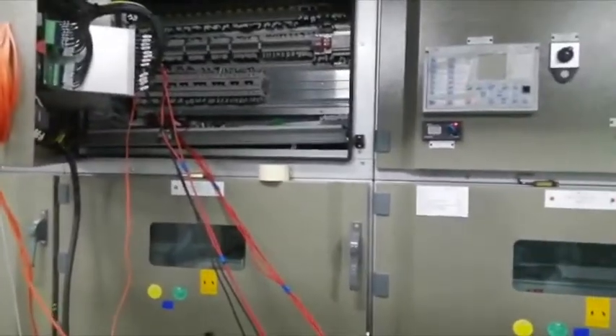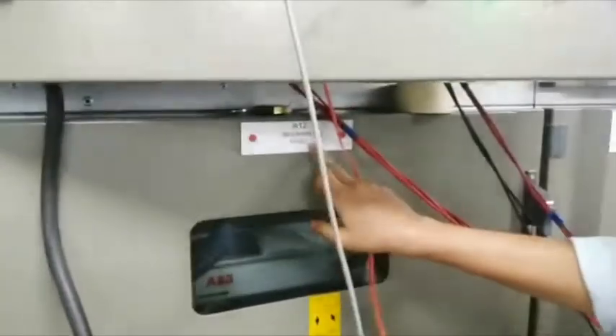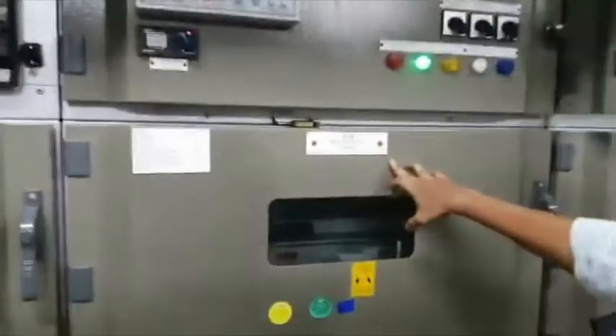Good morning, sir. This is Dharmaraj, production engineer. Today I am going to test the differential protection of 11 kV switchgear panel. This is our A12 incomer 1 panel. This is our A13 bus coupler and A14 bus riser, and our second panel, second incomer A15 incomer 2.